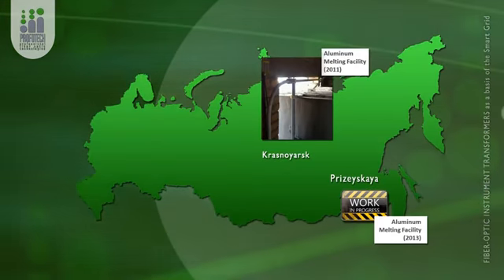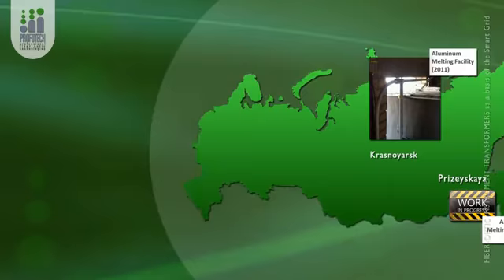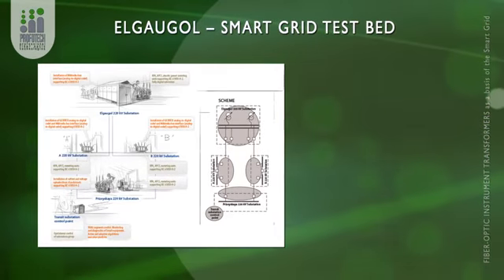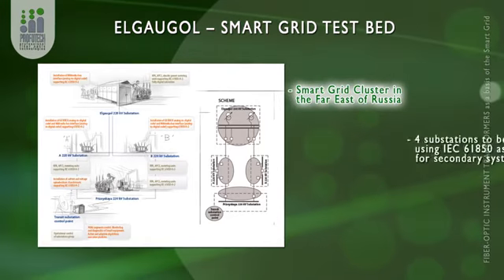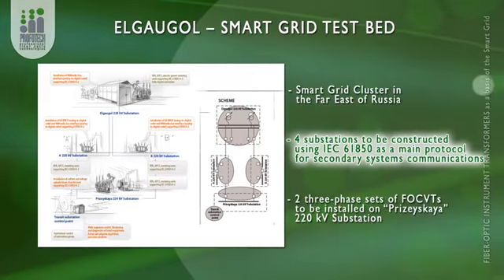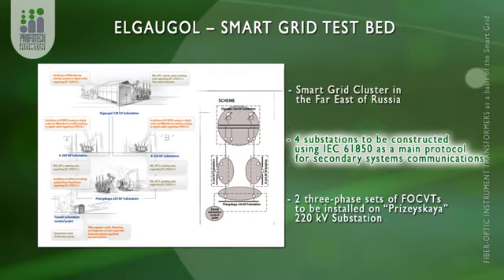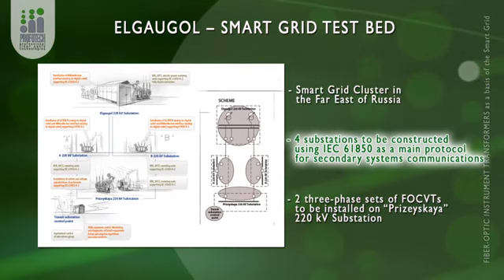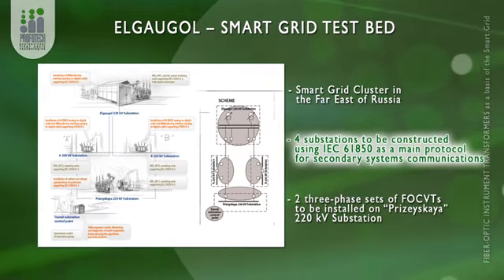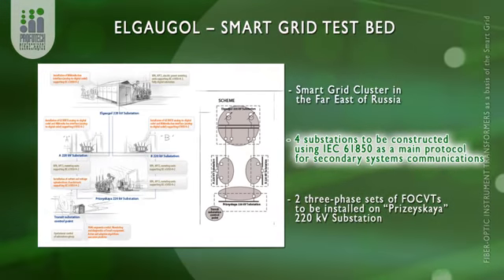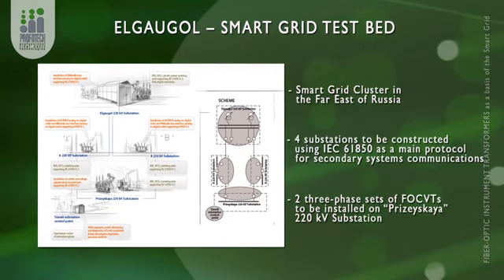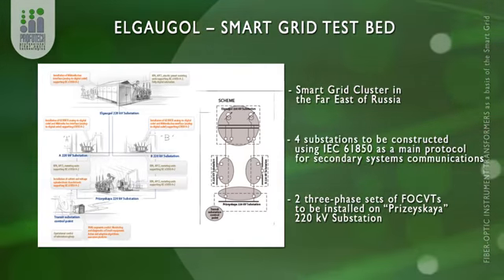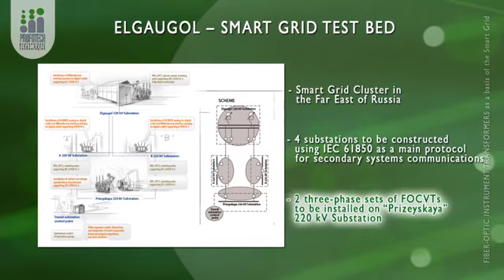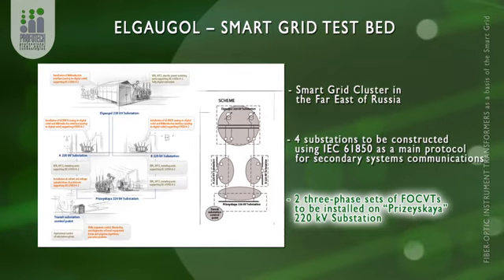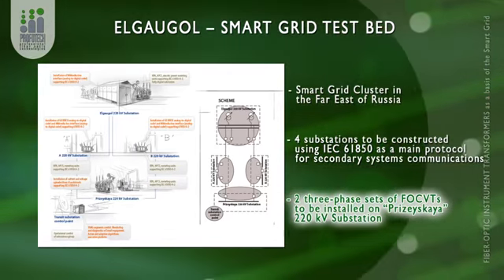Since 2012, they have proven to be efficient and resistant to great electromagnetic fields due to high currents there. Project number 2 is a very interesting project, which is located in the far east of Russia. This complete cluster is referred to as the test bed for smart grid. This is a cluster of 4 substations which is going to use the IEC 61850 standard to process all communications in the substations, including the IEC 61850-9-2 process, goose messages, MMS, etc. Of the 4 substations, Profotech will install the instrument transformers on one of them, and there will be 2 3-phase sets of combined current voltage sensor for 220 kilovolts.